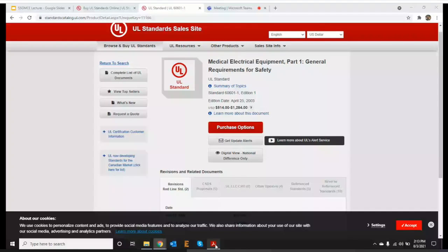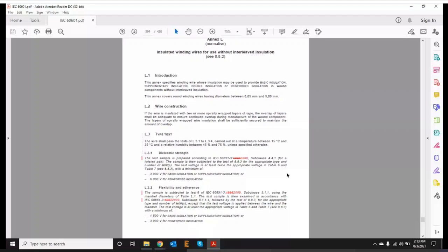This tells you the introduction, the wire construction, the amount of overlap and clearance and creepage in your particular device, your PCB layout, what the tests will be, at what temperatures they will be testing it. If you say it will work at nominal room temperature, then it will be tested for 15 to 35 degrees Celsius. If you say it can be used for a higher temperature range, then a 50 degrees Celsius test will be carried out.